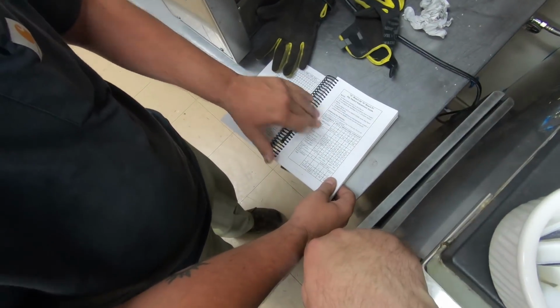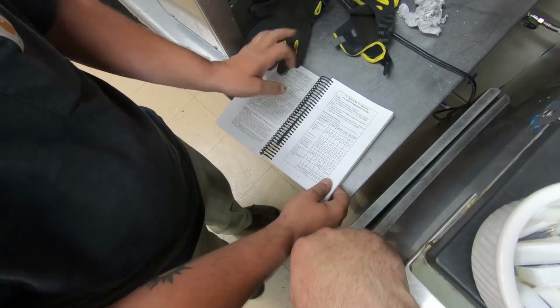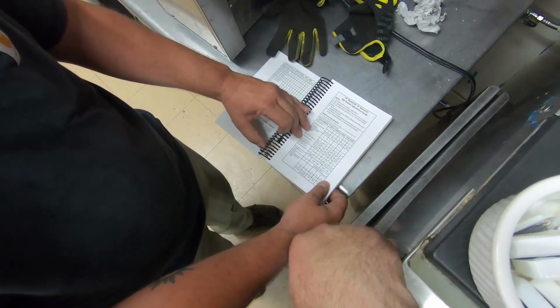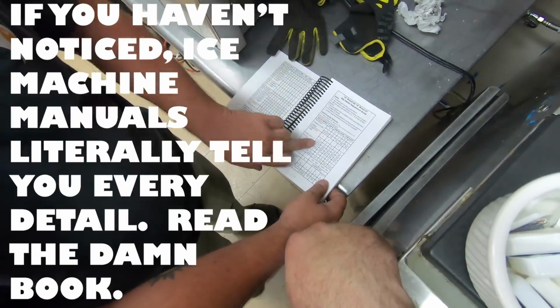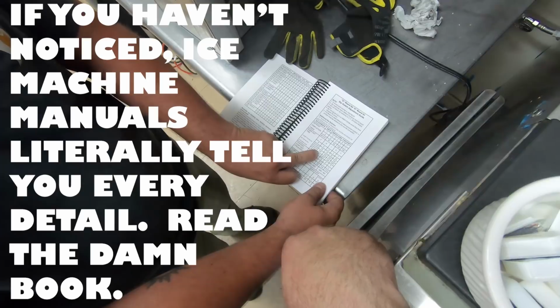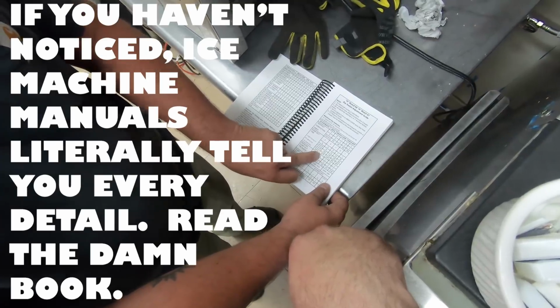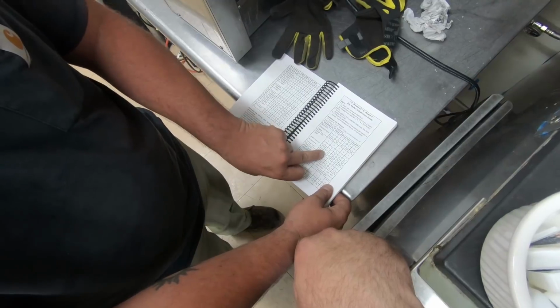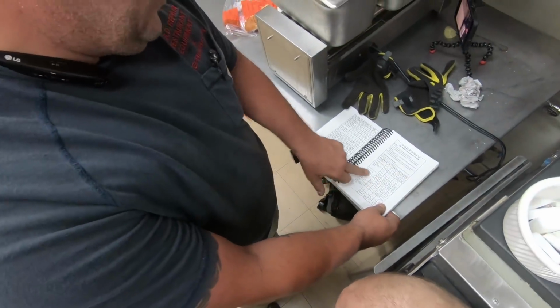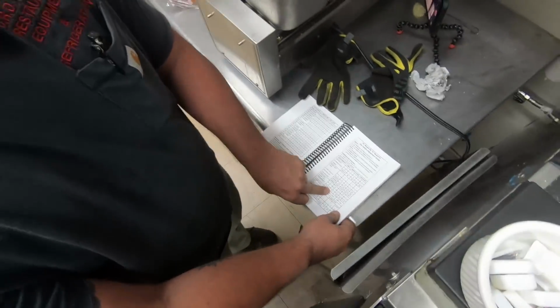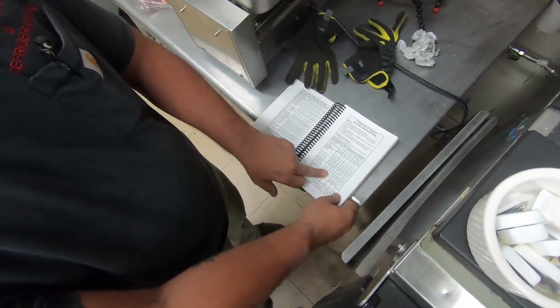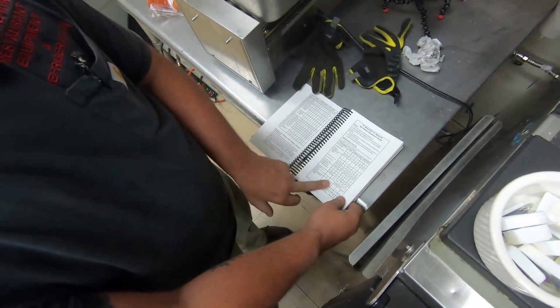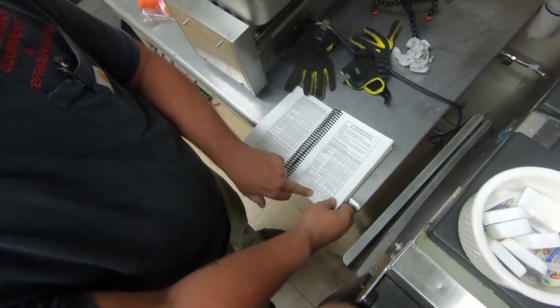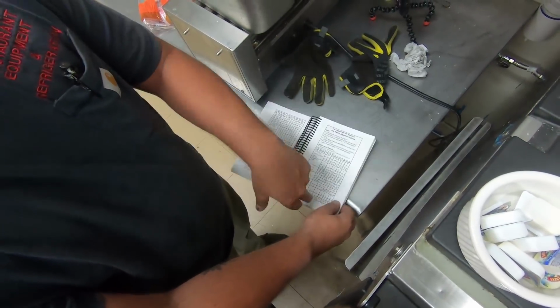Gauging up is always a last resort. Dip switches 1 and 2 are the defrost completion. We have this one set for 180, that's 180 seconds. Then your pump out is your purge. This one is currently set to do a 10-second purge with the water inlet, or 10-second pump out, the water inlet for off, and then it's doing a periodic pump out every cycle. So this one is set to do it every cycle, just because I know what the dip switches are set at now. 8 is always off, and max freeze time on this one is set for 70 minutes. So here's your 10-pin connector.